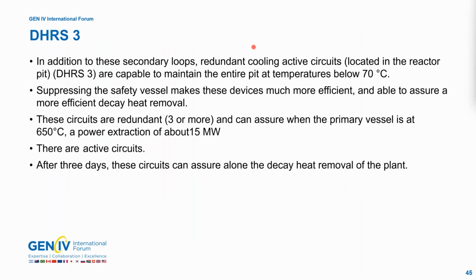So DHRS 3: we have already spoken of these 2 active cooling circuits located in the reactor pit, able to maintain the entire pit at temperatures below 70 degrees. We have suppressed the safety vessel, which makes the device more efficient than before. The circuits are redundant, 3 or more, and can assure, when the primary vessel is at 650 degrees, a power extraction of about 15 megawatt. They are active circuits, not passive circuits. And after 3 days, the circuit can assure alone the decay removal of the plant without the secondary loops.